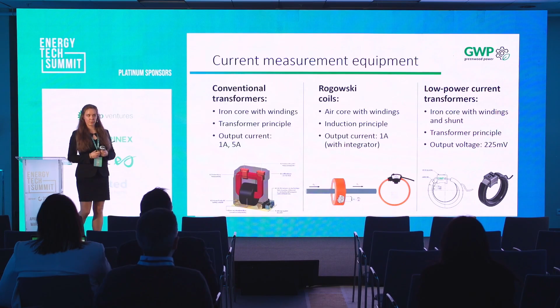Now let's look at current measurement equipment. Here you have three principles. The first, again, is a conventional transformer. The next is the Rogowski coil, and the third is a low-power current transformer. I don't have the low-power current transformer with me, but it's basically the same size as this product.